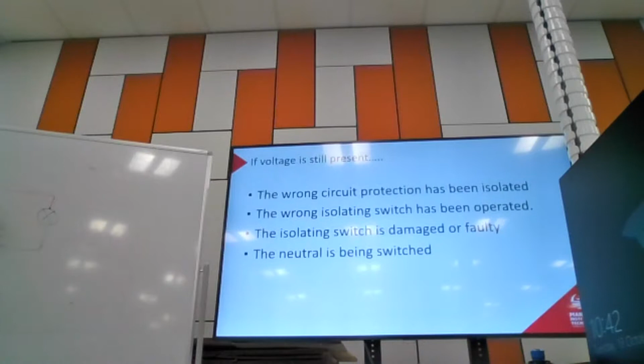The only time I've come across it that was particularly bad is in a situation where we had 2-pole switches. So the neutral and phase were switched. They were done deliberately. But there were like 6 isolators next to each other, and someone had run the phase for one equipment through one switch, but then the neutral back to a different switch. And so then the phase on that one to a different equipment and the neutral on that one. So they'd switch the neutrals over at the switch, which I won't go into all the details because it'll take hours, but it worked perfectly fine. Because as long as those neutrals are continuous and everything is switched on, it's fine.